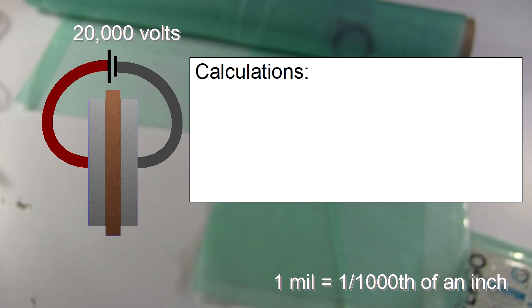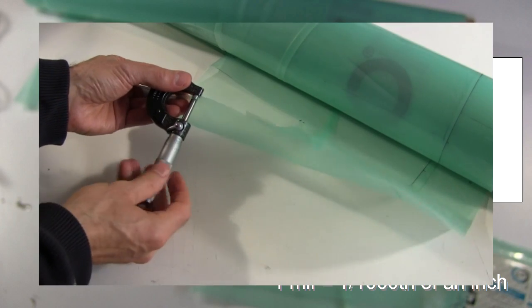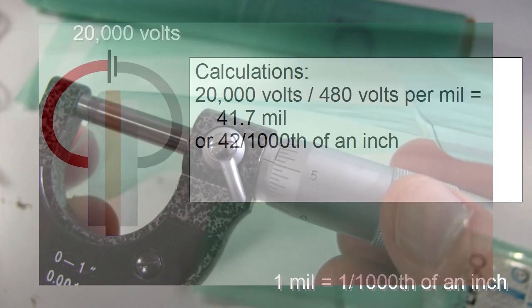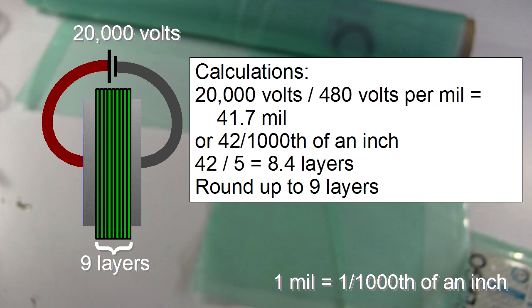Let's say we want to be able to handle 20 kilovolts, or 20,000 volts. 20,000 volts divided by 480 volts per mil gives us a thickness of 41.7 mil, and that's 42 one thousandths of an inch. If I take my calipers, I find that a single thickness of polyethylene is five one thousandths of an inch. So 42 divided by 5 tells me that 8.4 layers of polyethylene will be thick enough to withstand 20,000 volts. Of course I'll round that up to nine layers, or even more for additional safety.